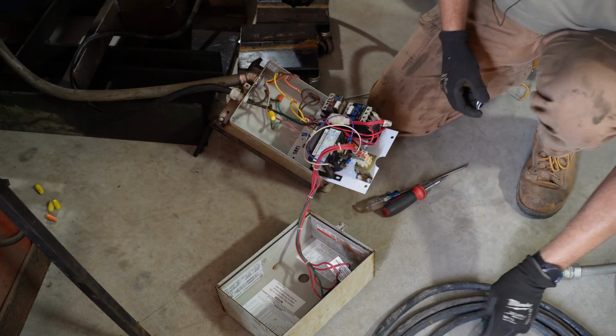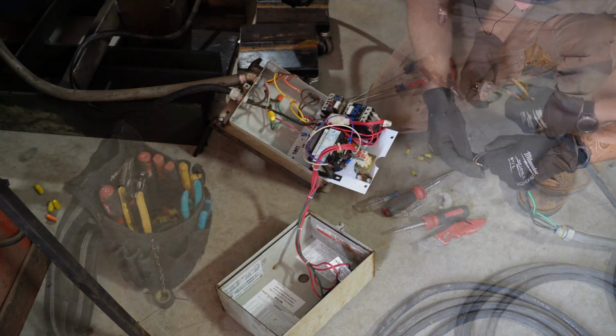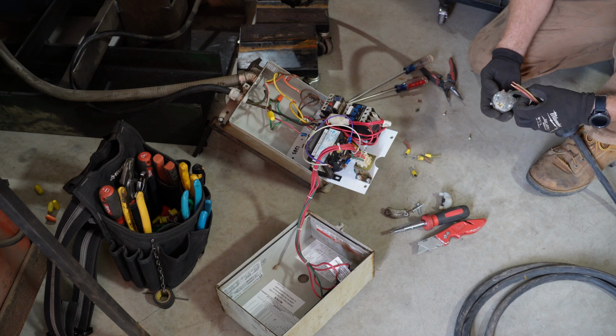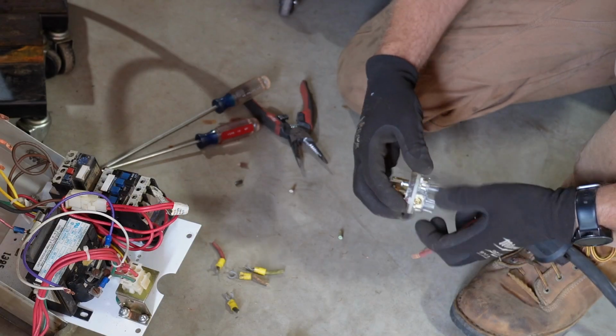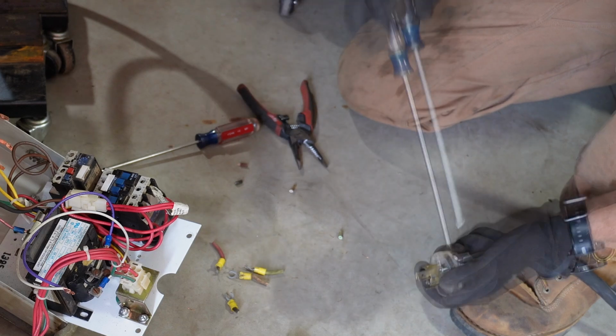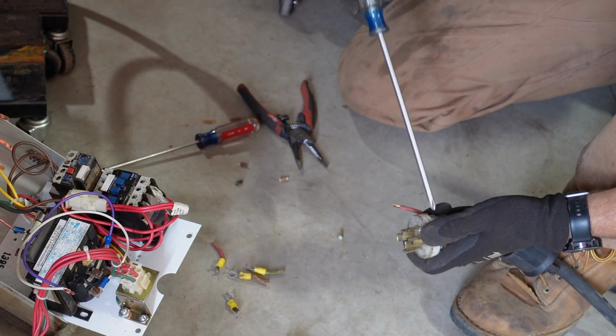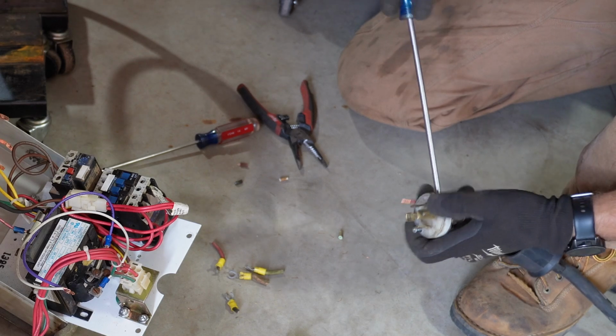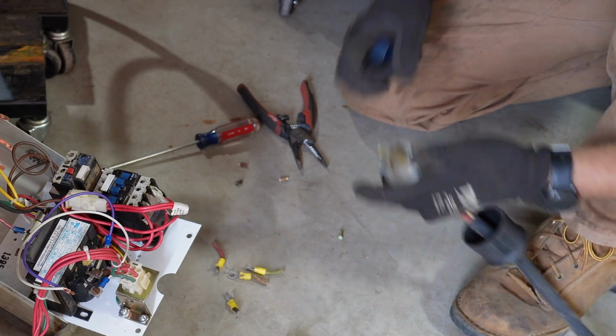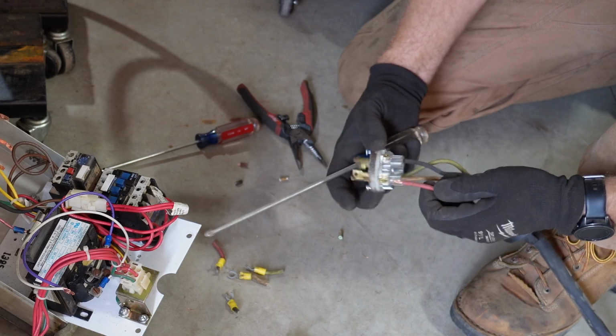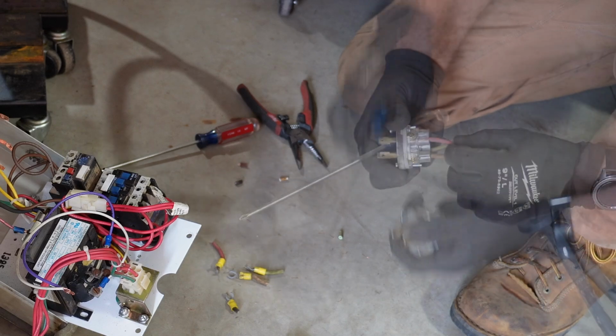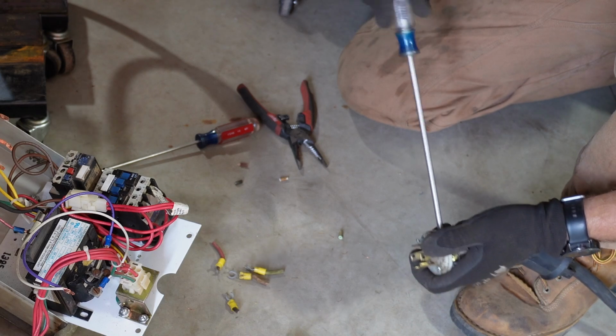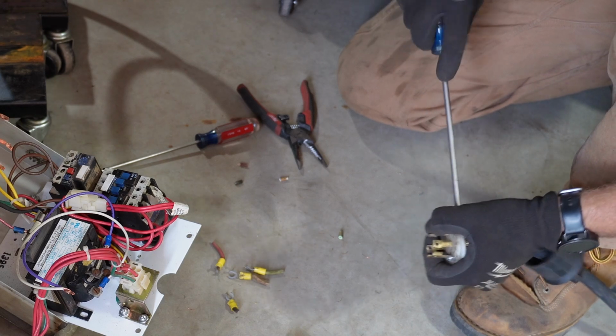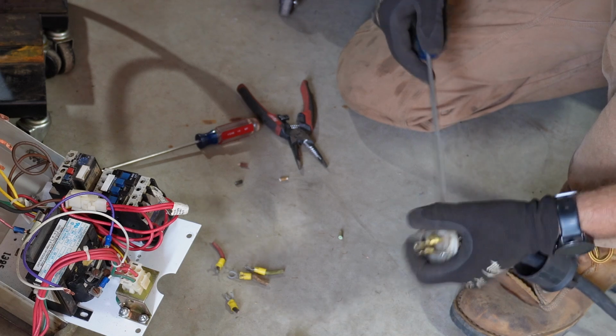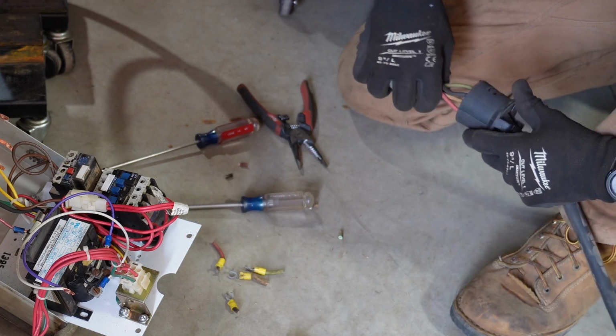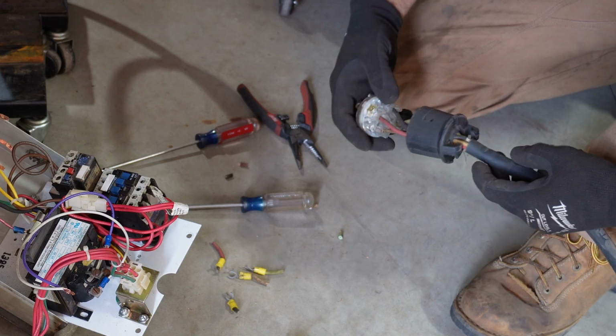All right, now I will set up my new power cord. Generally speaking, these don't matter - I've found that the 3-phase motor doesn't really care which terminal it gets. However, the first time I fire this up, it's spinning the wrong way. All you have to do is swap any 2 of these and you'll reverse the direction of the motor. A lot of VFDs have the ability to just hit reverse, but the one I'm using, I struggled with that when setting up the other one. So I'm not even gonna bother - I just found it's easier to do this. I made that way too long, didn't I?